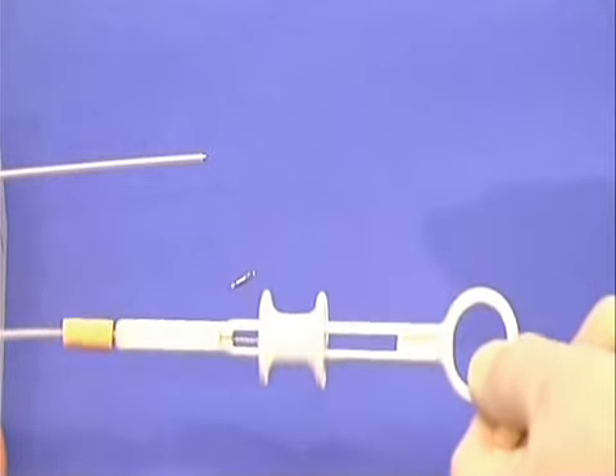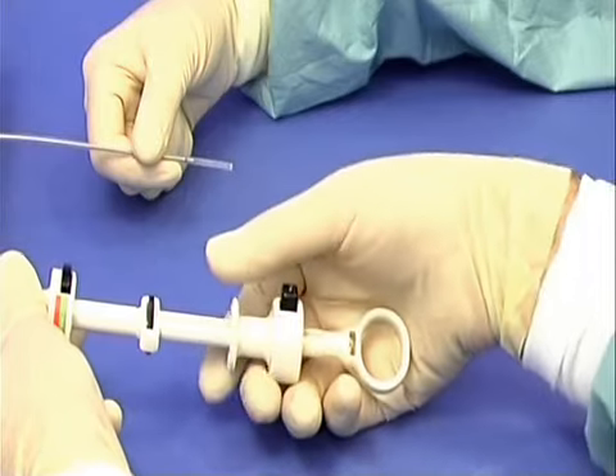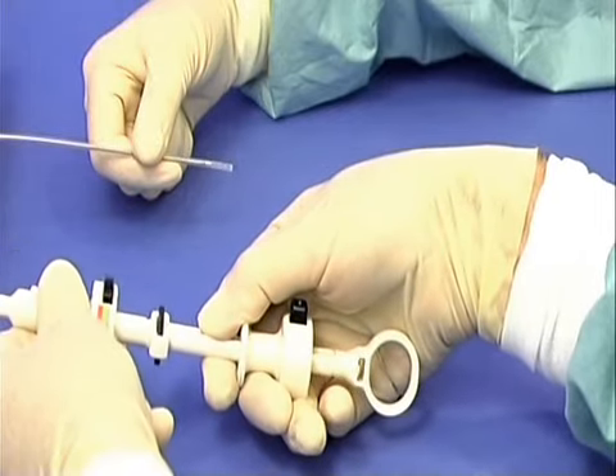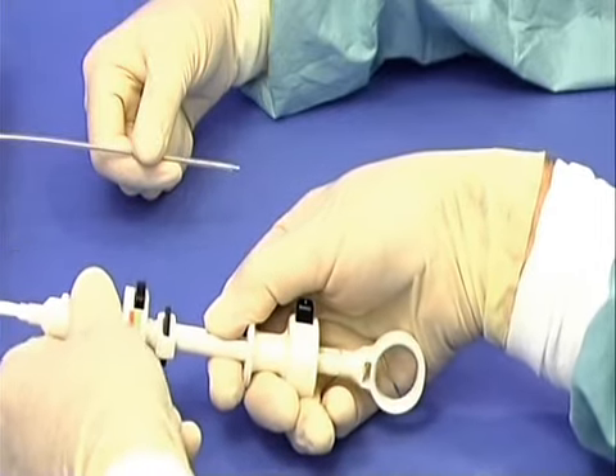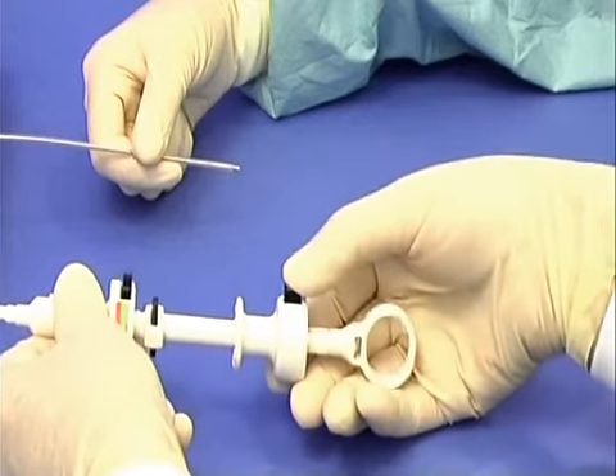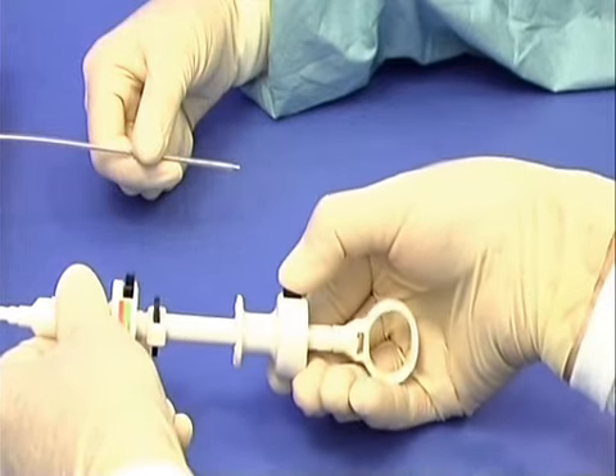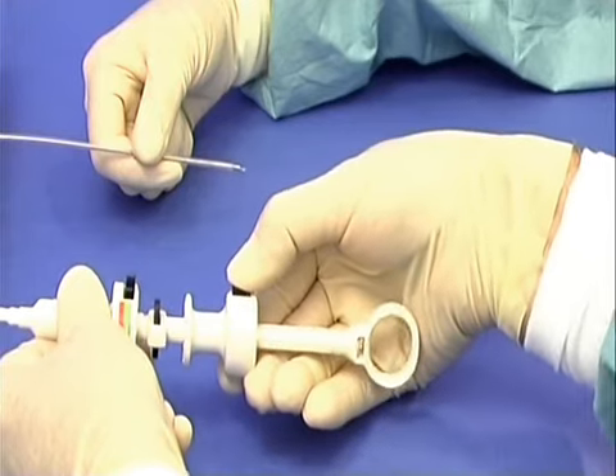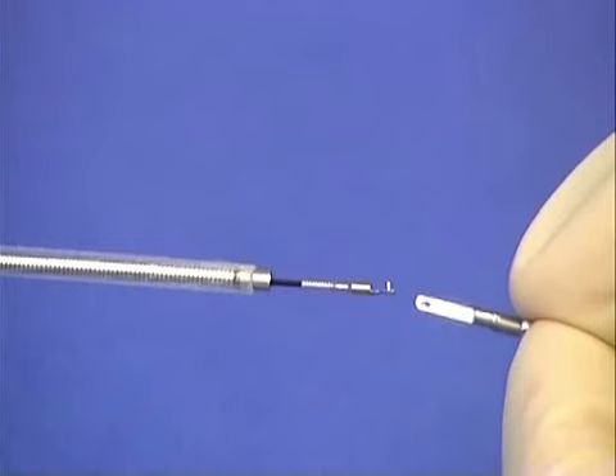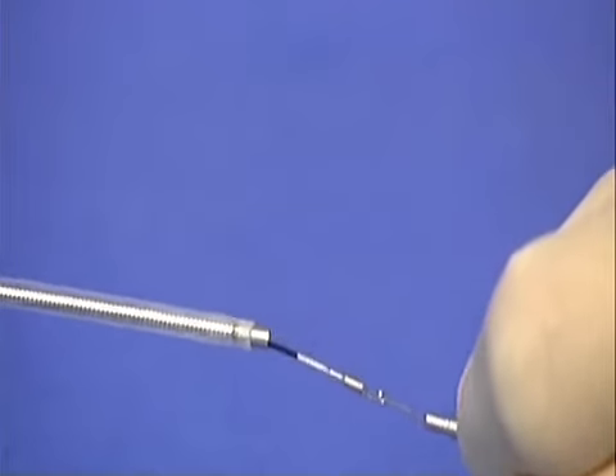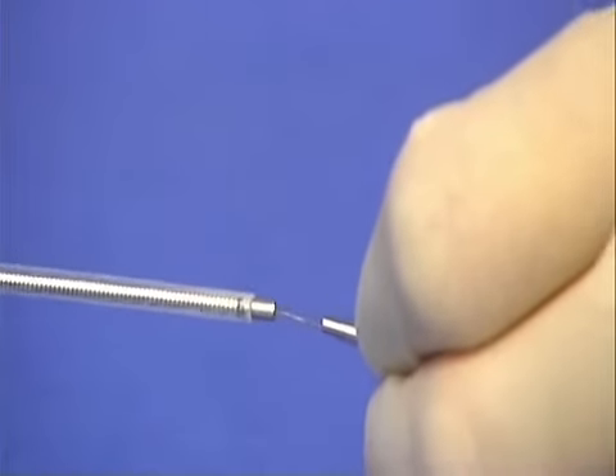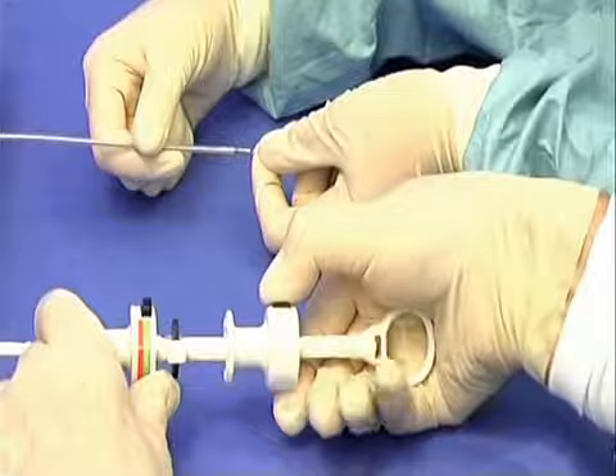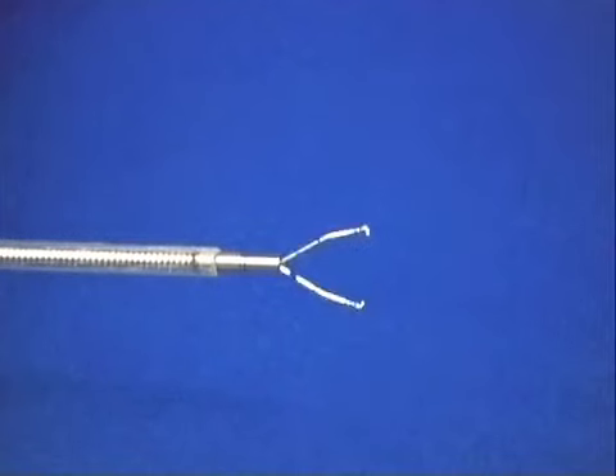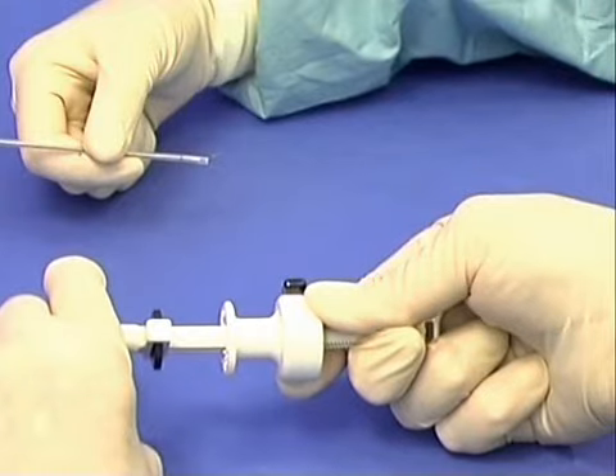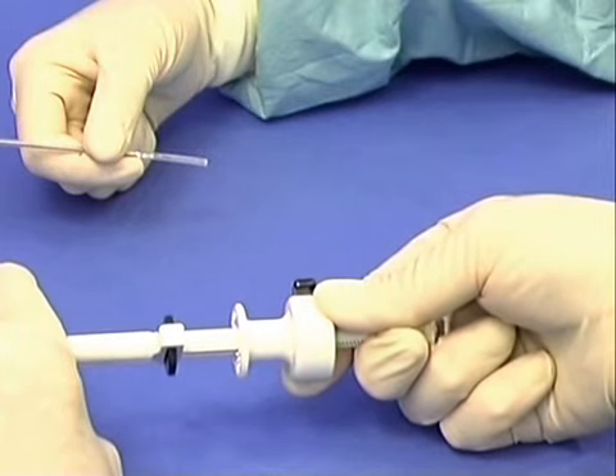The reusable clipping device has a different handle mechanism. Pull back the outer sheath to expose the metal inner coil, press down the black button and push forward the slider to protrude the hook. Attach the clip onto the hook, then retract the hook into the inner coil by pulling back the slider a little. When it's open like this, the clip can be rotated, but cover it for insertion by sliding out the outer sheath again.